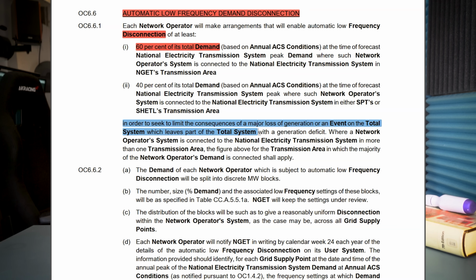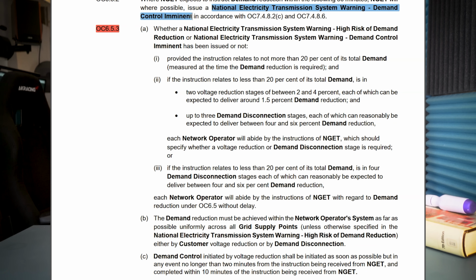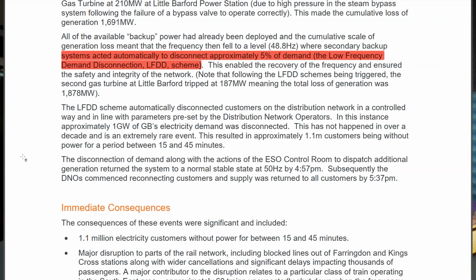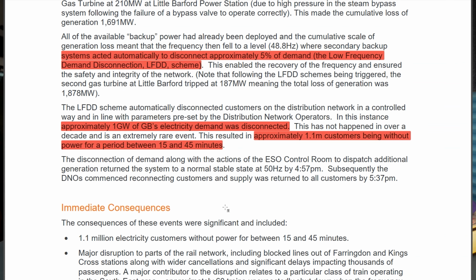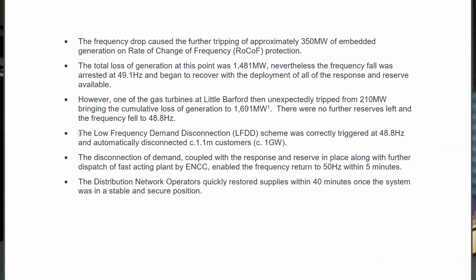LFDD is a last resort protection where the system automatically sheds parts of the national demand to prevent total collapse. It operates in stages, with each stage set to activate if frequency keeps dropping. Each stage typically disconnects 5 to 10% of national demand, up to a total potential of about 60% if needed. So in 2019, only the first stage was needed, cutting about 5% of national demand and affecting 1.1 million customers.